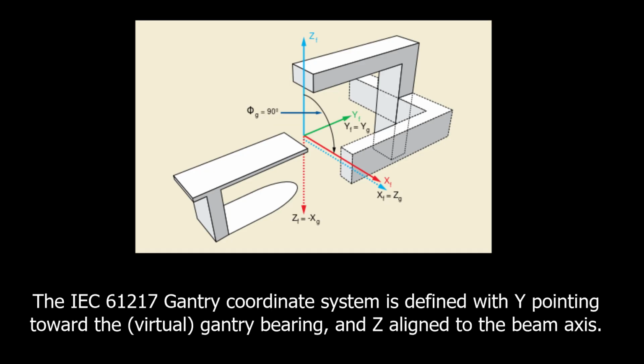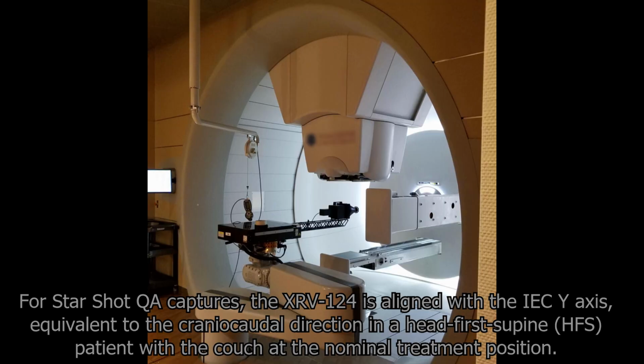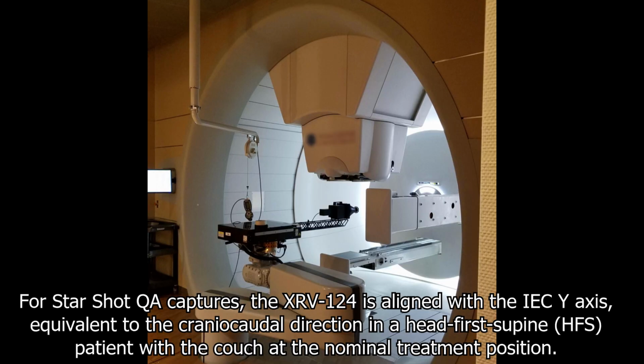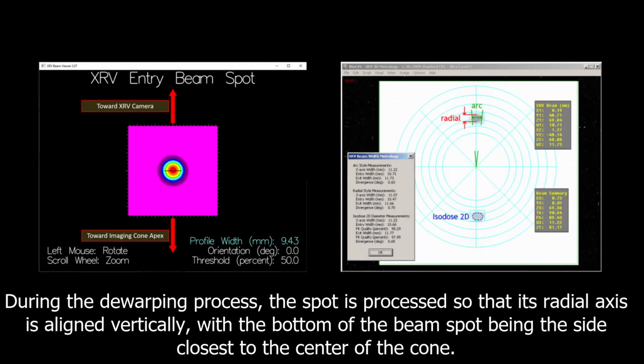Let's take just a minute to talk about the beam spot coordinate conventions. Generally speaking, the XRV is going to be aligned with the y-axis of the IEC gantry coordinate system. So the camera is going to be aligned with that y-axis, and it's going to be seeing warped beam spots all around the center depending on the gantry angle. But when those beam spots are dewarped, they also get indexed so that the radial direction is always vertical. The bottom of the beam spot is the side closest to the apex of the cone.